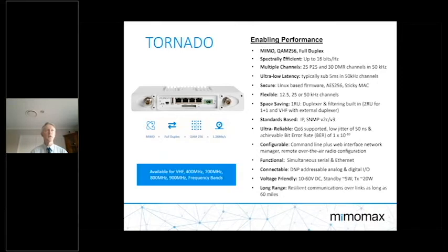Some of our users operate it as a small RTU, so it supports DNP3 addressable I/O. We use that sometimes to control and monitor doors, and because it's got an analog input and ADCs at the input to that I/O, you can also manage and monitor analog signals such as battery voltages or temperature, which some of our customers do.